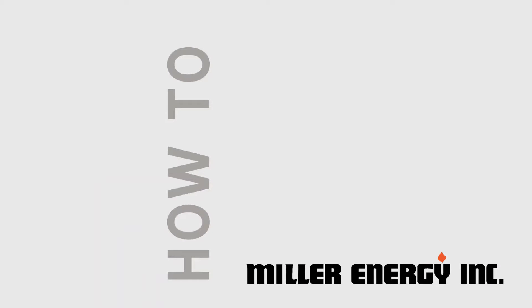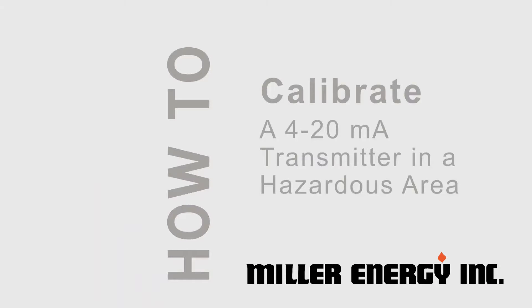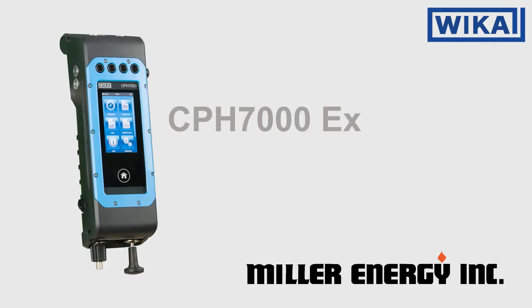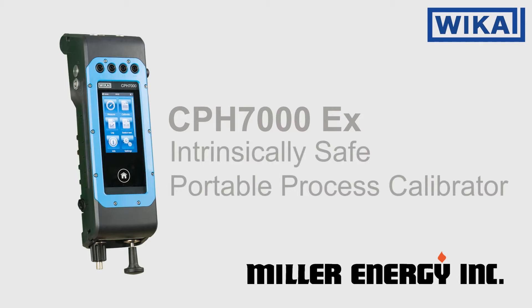In this video we'll show how to calibrate a 4 to 20mA pressure transmitter in a hazardous environment. We'll use the WIKA CPH7000 Intrinsically Safe Portable Process Calibrator to program the calibration sequence.